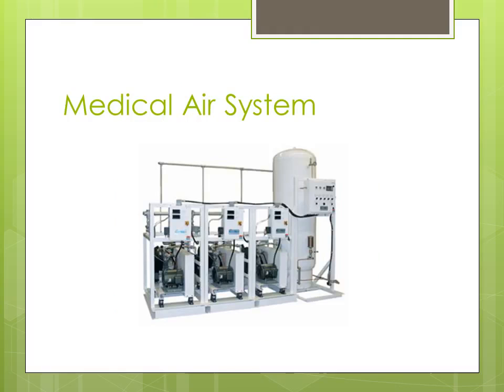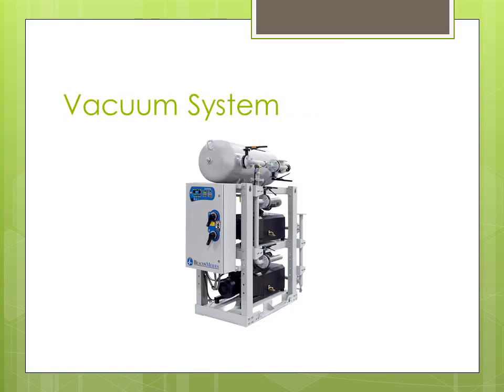Here's an example of a medical air system. One thing to keep in mind about medical air is that when you deliver medical air, it needs to be very, very clean, obviously, and it also needs to be dry. So on most medical air systems, you'll find either some type of refrigeration system that dehumidifies, or you'll find desiccant filters that are used to dry. And of course, both those systems require a fair amount of maintenance. I think that's the one thing that sometimes gets missed with these medical air systems. Otherwise, they're compressors and motors, and just the storage tank.